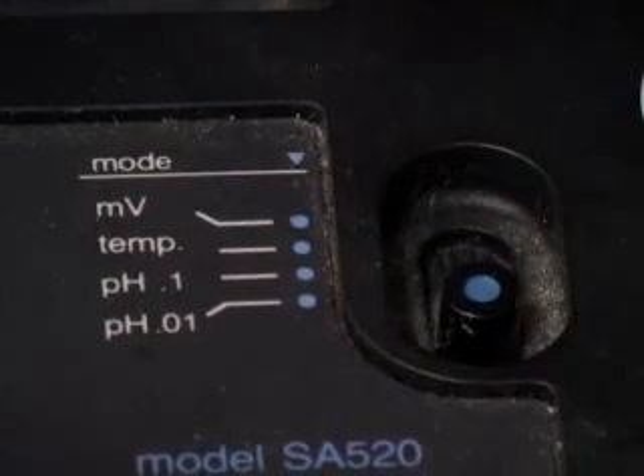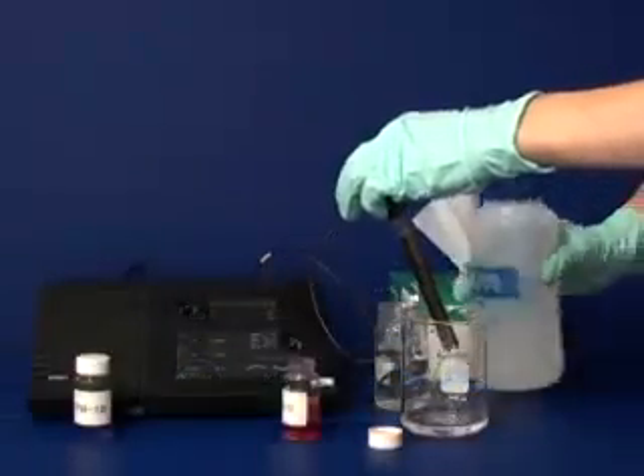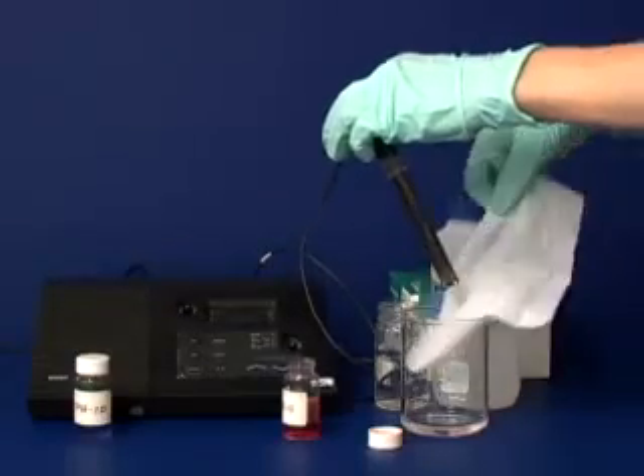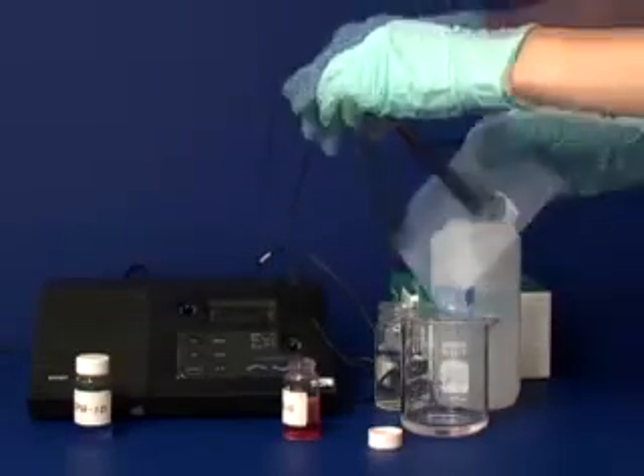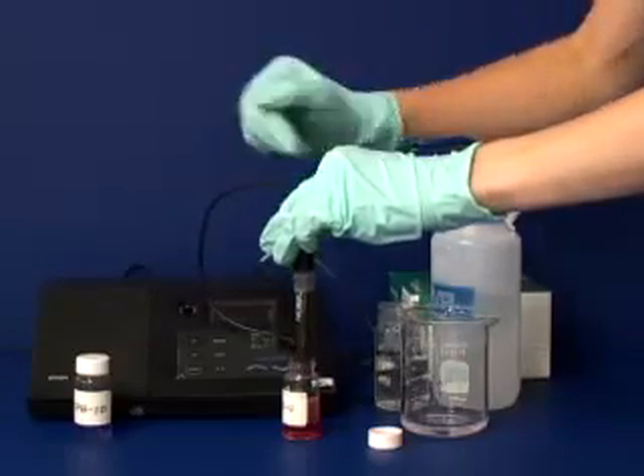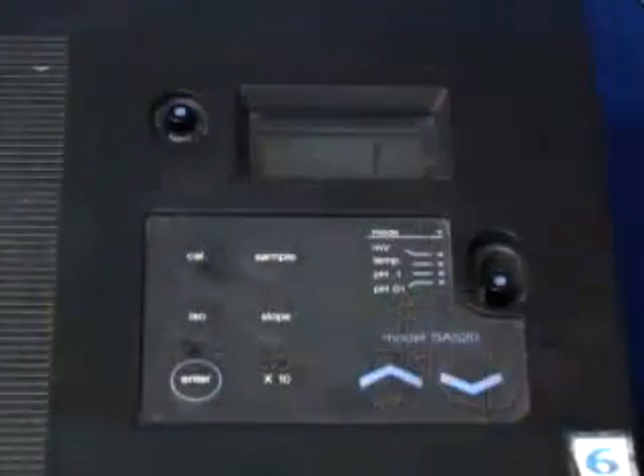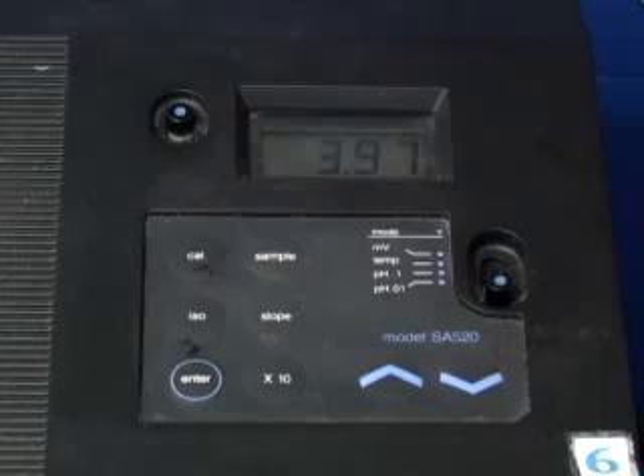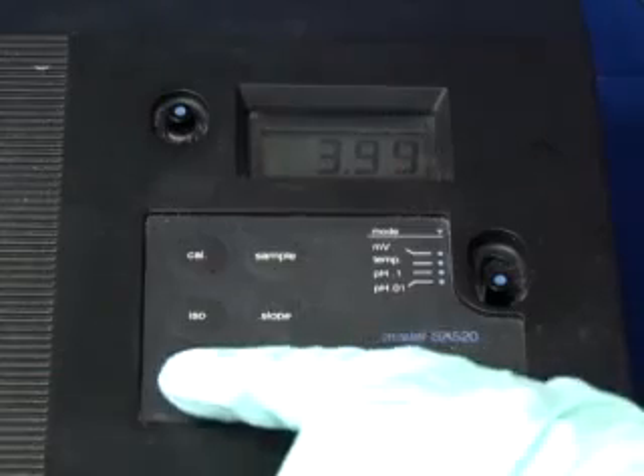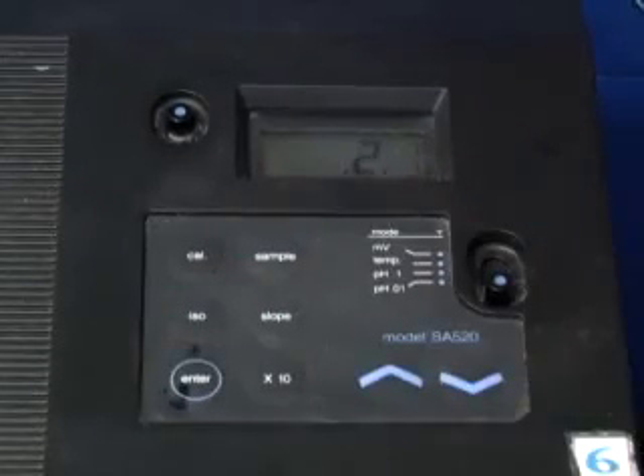Turn on the instrument and select the pH mode as 0.1 or 0.01. Then press the ISO button and verify that the pH reads 7.00. Rinse off the probe with distilled water into a waste beaker and gently blot it with a Kim wipe. Place the probe into the first buffer and press the Cal button. The number 1 should appear on the display. The display will alternate between 1 and the pH value of the solution. Wait until the display stabilizes and press Enter. The number 2 should then appear on the display.